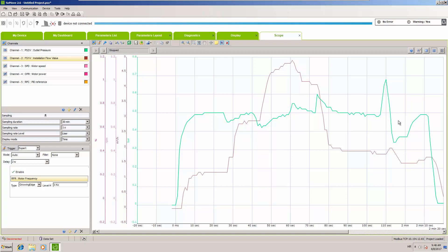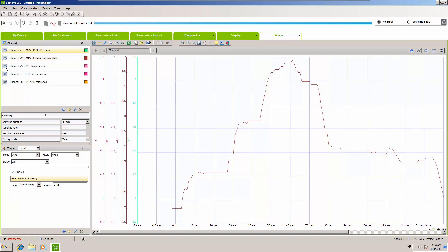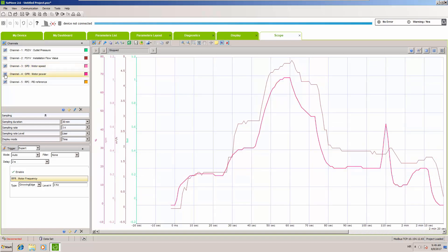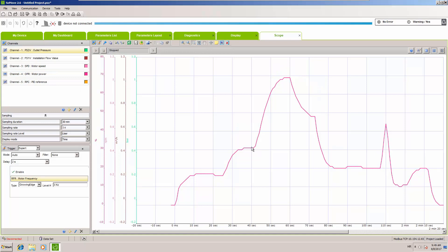One more interesting observation: if we compare installation flow with motor speed, we can see a clear pattern — as flow goes up, speed goes up; as flow goes down, speed goes down. Looking at motor power, it is even more visible that motor power is directly connected with installation flow and not with pressure. That is it for our advanced PID video — hope you enjoyed it and catch you next time.